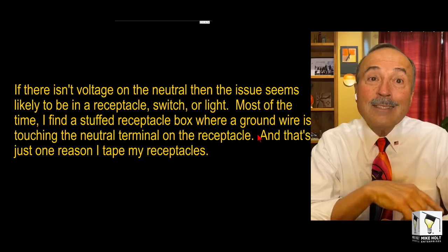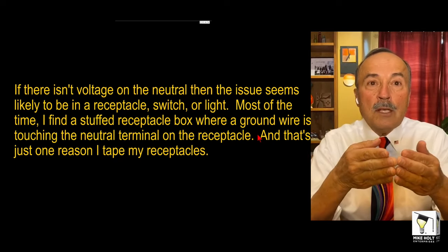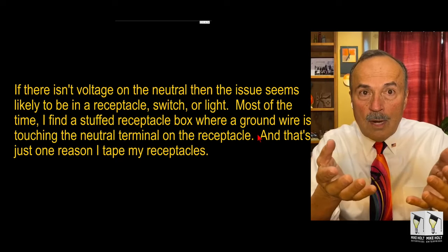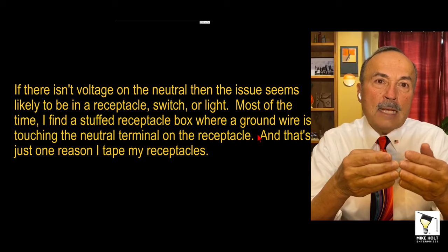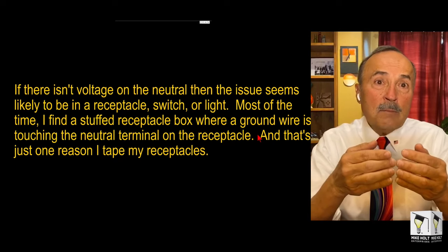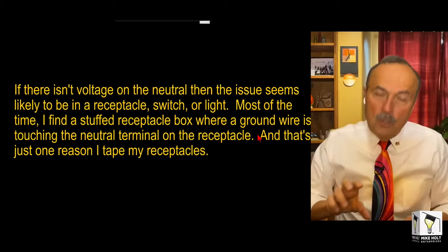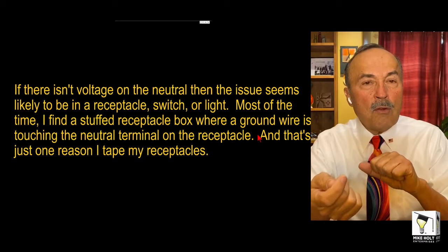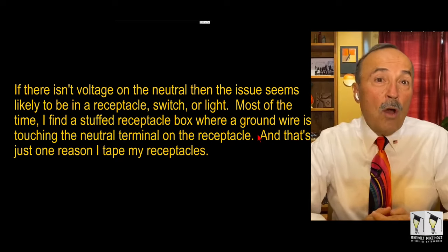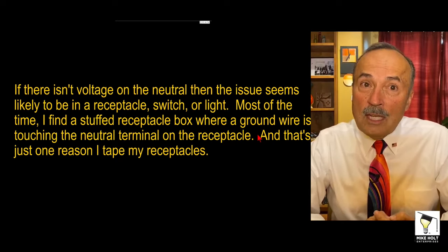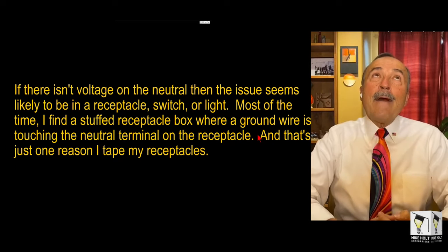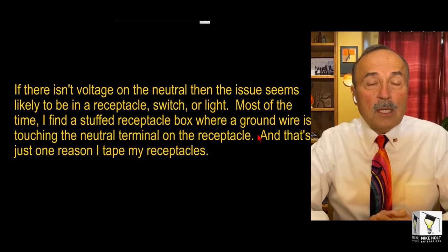What that means is that somewhere in a box, your equipment grounding conductor, your ground wire, your bond wire, is possibly making a connection to a phase conductor or to the neutral. In other words, you push in the wires, and then that bare equipment grounding conductor touches the neutral, and that will also cause GFCIs to trip. And that would cause an AFCI to trip because the current goes out on the hot, your neutral is touching the equipment grounding conductor, which means not all the current is returning on the neutral because it's going to divide onto the equipment grounding conductor, so the AFCI would trip.